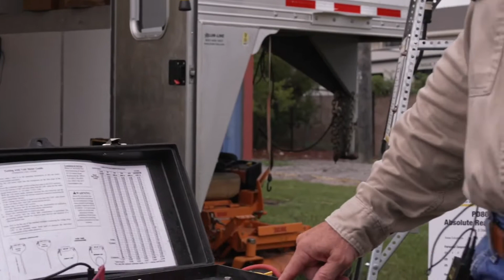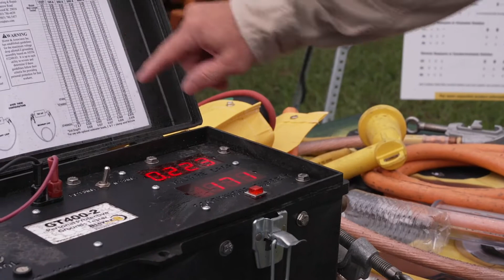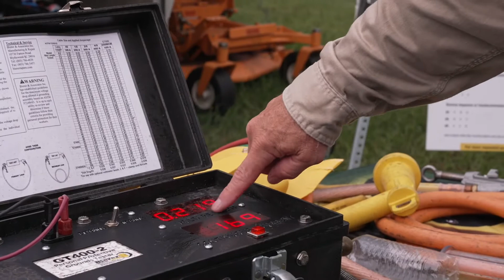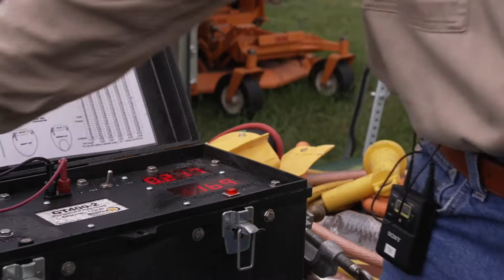That's the continuous current meter here. We're looking for a little over 165 amps, which is required on the chart, and a 0.24 voltage drop or less for this to pass. You can see 0.22, let's just call it.